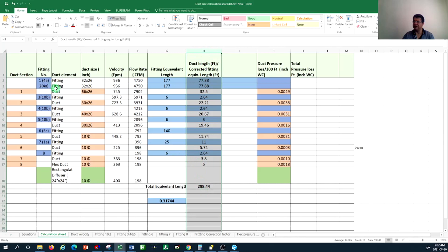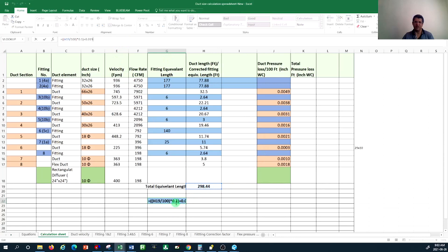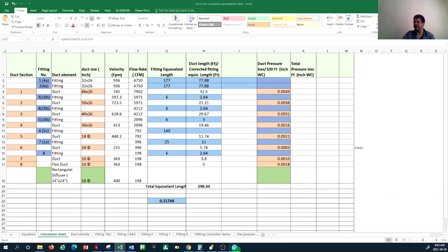After doing that, I add together all my equivalent lengths — including fittings and duct — and arrive at a total of 298 feet of duct work. To calculate the static pressure I simply multiply this by 0.1 inch water column per 100 feet, then divide by 100, and I get the pressure drop across the entire duct work including fittings as 0.3 inches. You could run it a little higher to 0.4 inches and still be within the range for the rooftop unit shown in the catalog.